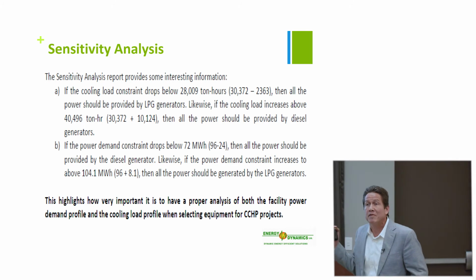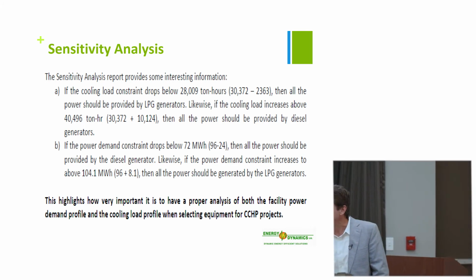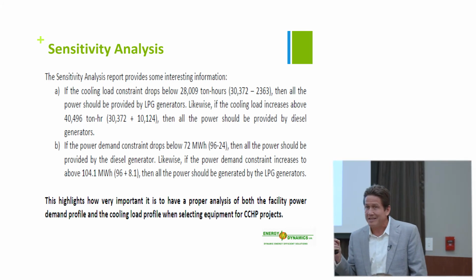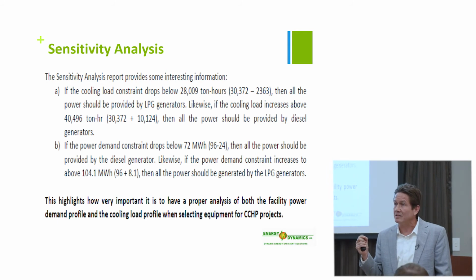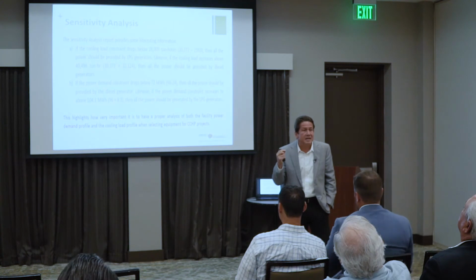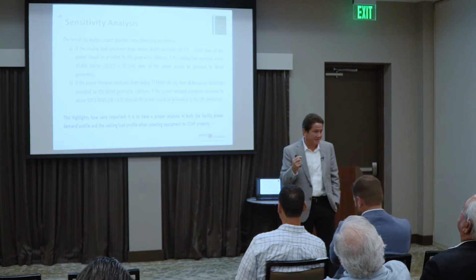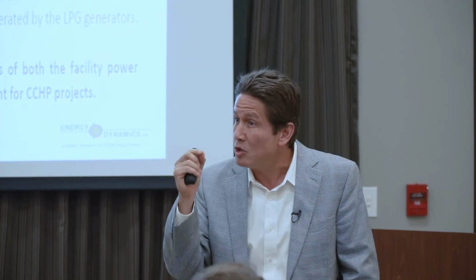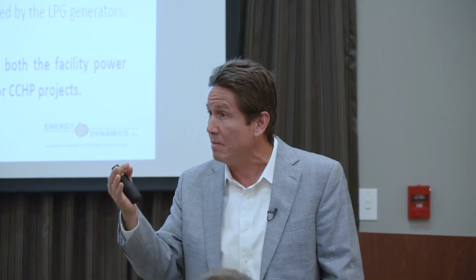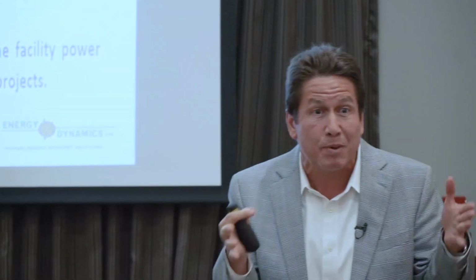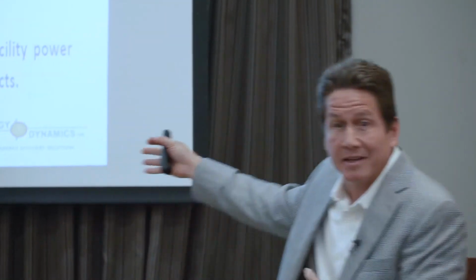You know what we found out? The information they gave us initially was incorrect. They said they're going to go up to a tonnage of 2,500 tons. No, they overestimated the cooling required. So a simple thing of not doing your homework and doing your energy, your heat load calculations properly - they overestimated the cooling, right? And that could affect your end result.